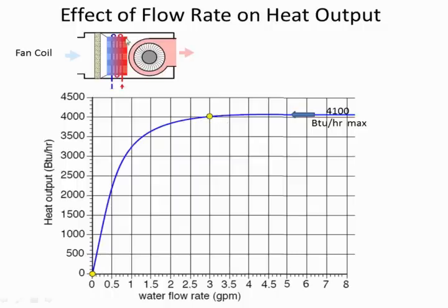So let's say that we have a fan coil that has a balancing valve on the same circuit, and we're targeting 3 GPM. So we set the balancing valve to be 3 GPM. Let us say the contractor made some mistakes and didn't quite do 3 GPM. He did 20% off of that. Let's take a look at the effect of that.